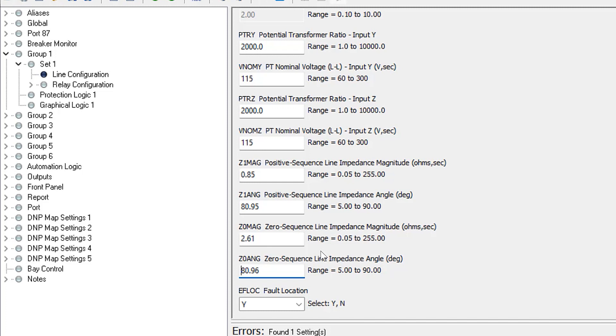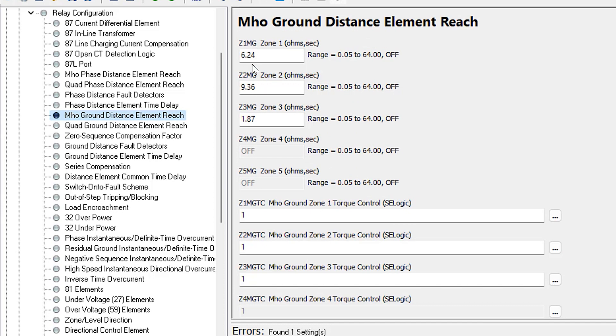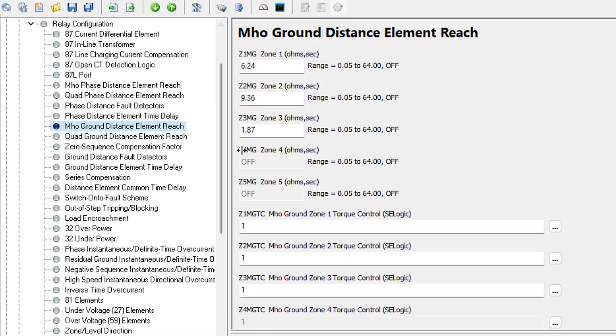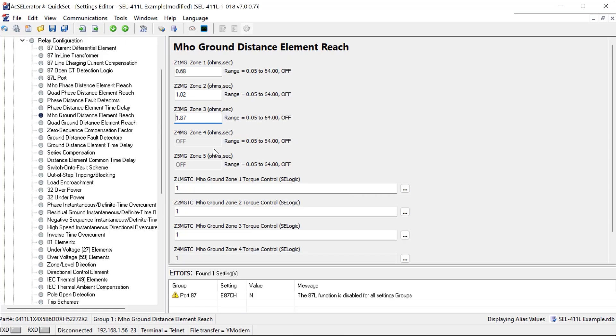Under relay configuration for mho ground distance element reach, we find Z1MG and Z2MG. Setting Z1MG = 0.68 ohms secondary (80% of positive sequence impedance) and Z2MG = 1.02 ohms secondary (120% of positive sequence impedance). The zone three element is set to off since we're not using it in this example.